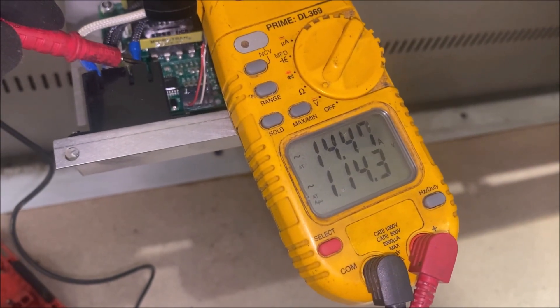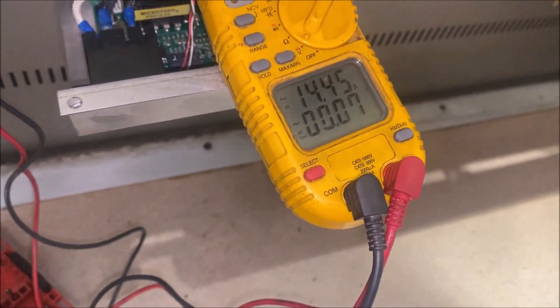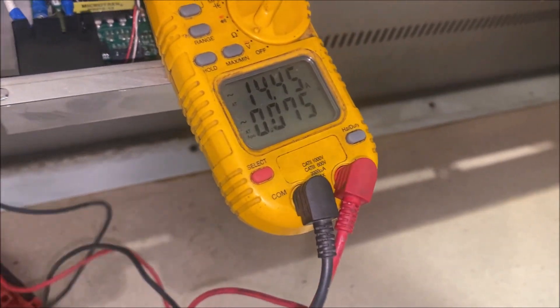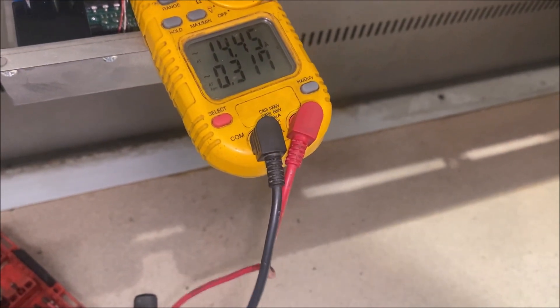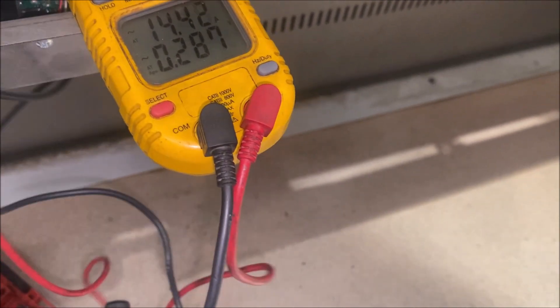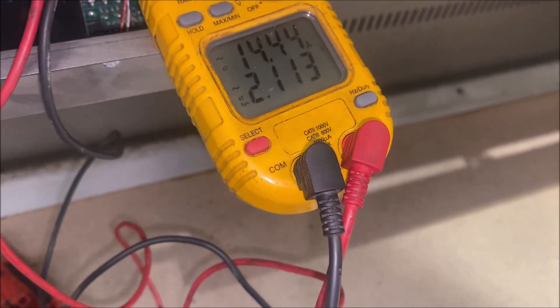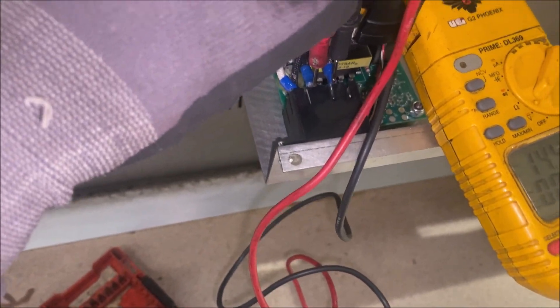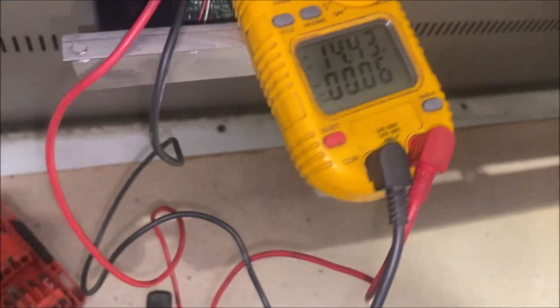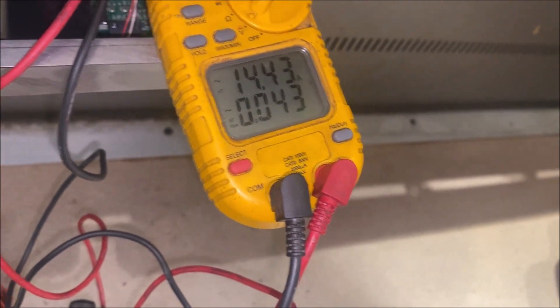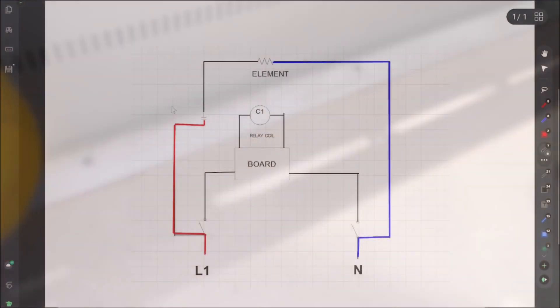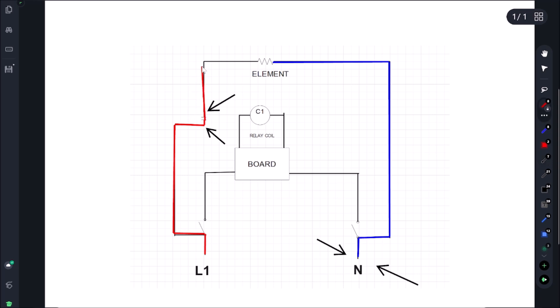Alright, so you can see here we have 115 volts at the outlet of the relay. We're going to test across for potential difference just to confirm. You can see there we're getting zero volts. So that's telling us the switch is closed. We tested power in to neutral 115, and then we tested power out to neutral one more time and we got 115. So what's that telling us? This relay is stuck closed.